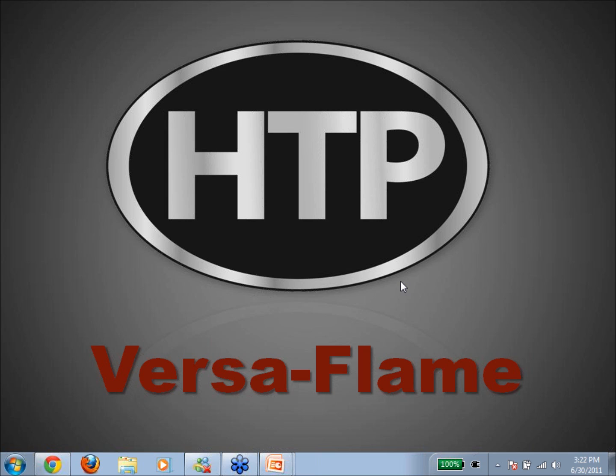Will HTP supply ModBus to BACnet or LonWorks adapter cards? I would assume... I don't think we've ever actually talked about whether we would supply them. They are readily available from a number of suppliers. So if they need to get an adapter or a link to communicate with the ModBus, those devices are readily available on the market. We could certainly recommend some at this point. If there's big enough interest, we could consider it, but right now, no, we won't. If we get enough feedback, please contact your regional manager, and then we'll bring it up.